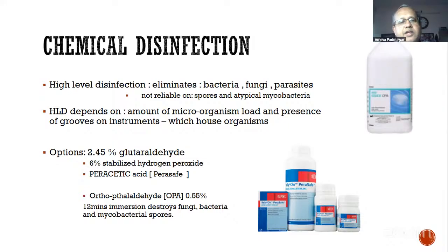Then comes the chemical disinfection. Now, why disinfection and not sterilization? Because it eliminates bacteria, fungi, and parasites, and it is not very reliable on spores and atypical mycobacteria. Remember that when you are using Cidex, that is 2.45% glutaraldehyde, which is available in all your ORs. You have to understand that once you activate this solution, it stays active for a period of roughly 14 days. Do not use it on the 15th day.